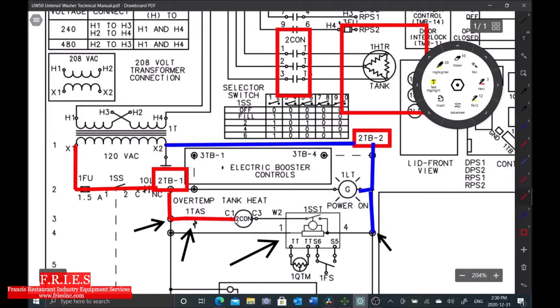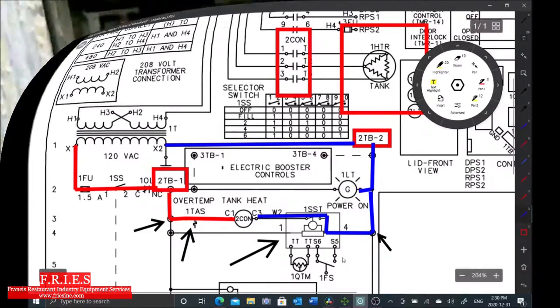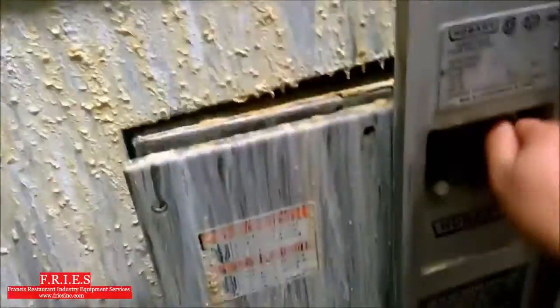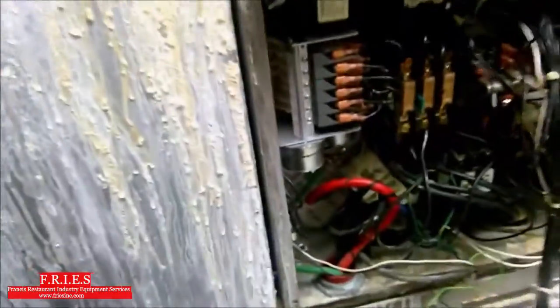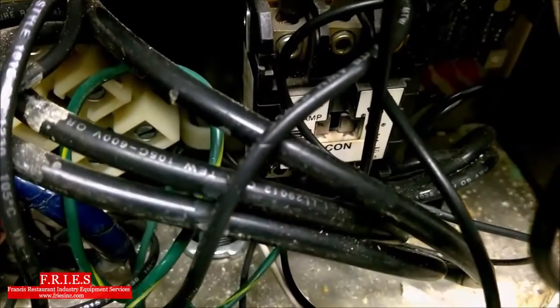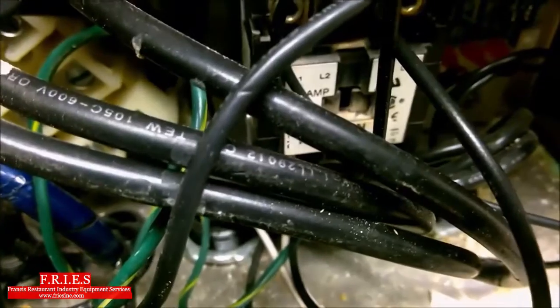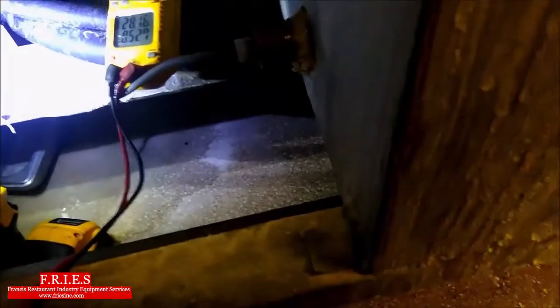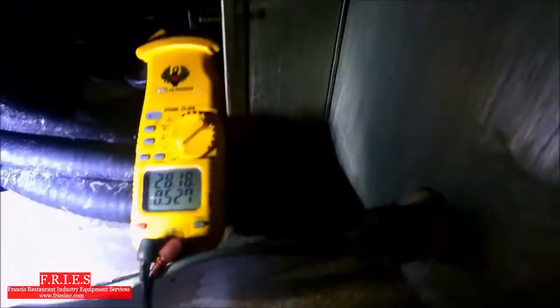Now it's closed and we can complete our circuit. We're going to come through here, and come through here, through our board. And now our contactor coil has power, and you can see the plunger pulling in on the contactor. Alright, so now I'm going to fire up the unit. You hear that contactor plunger pull in, it clicked in. You can visually see it's pulled in now. So we do have proper coil voltage at this point. So now I'm going to move over to the element. So this is on the left hand side of the unit.